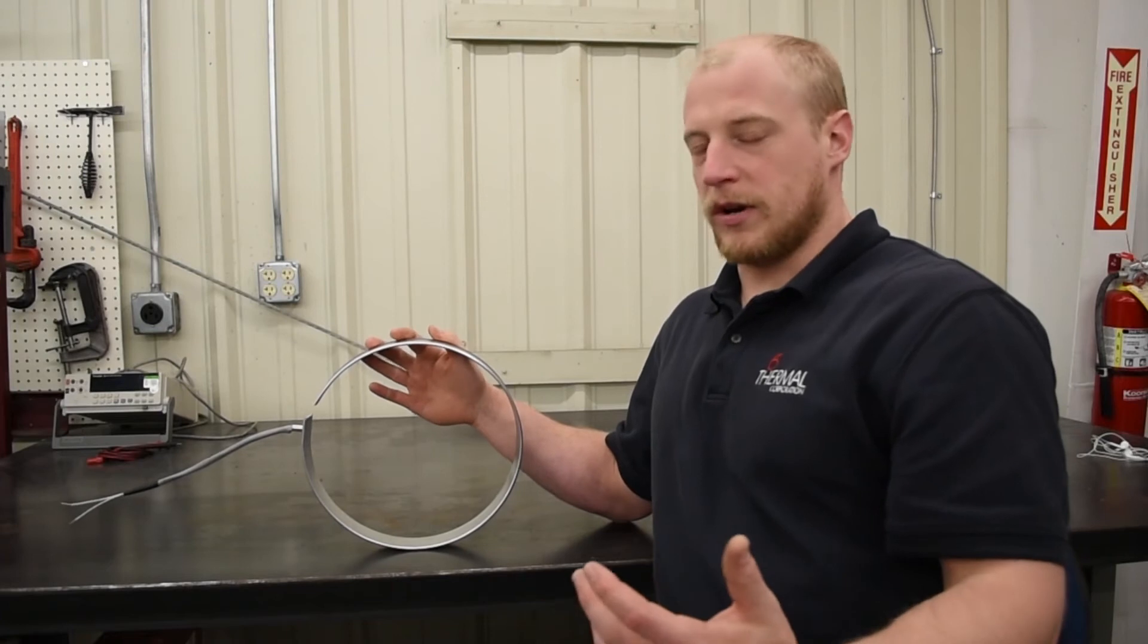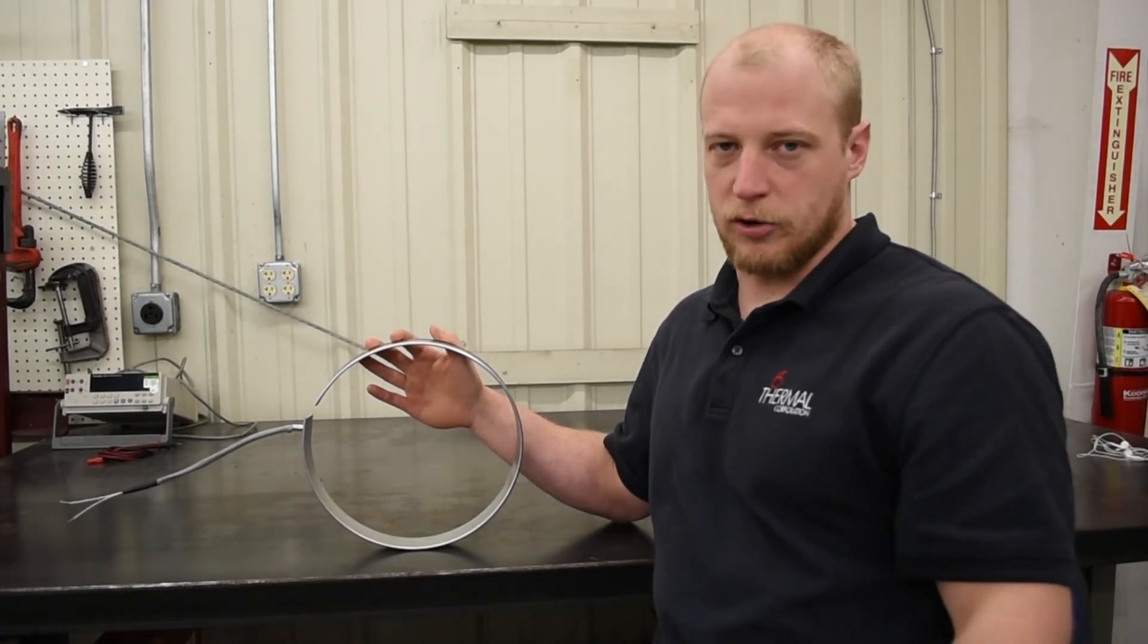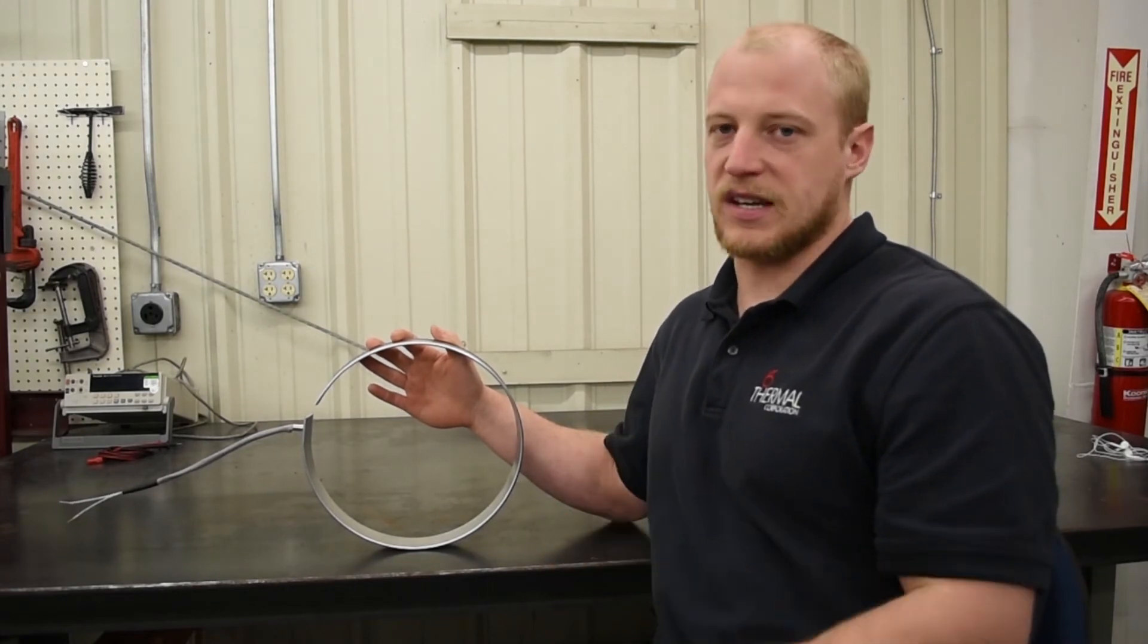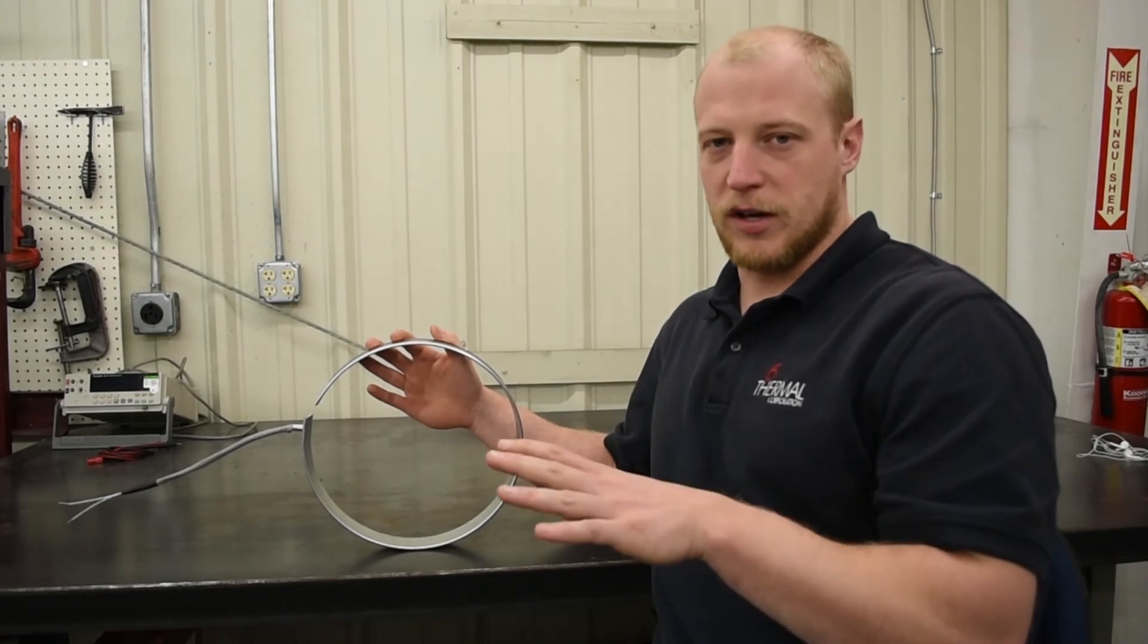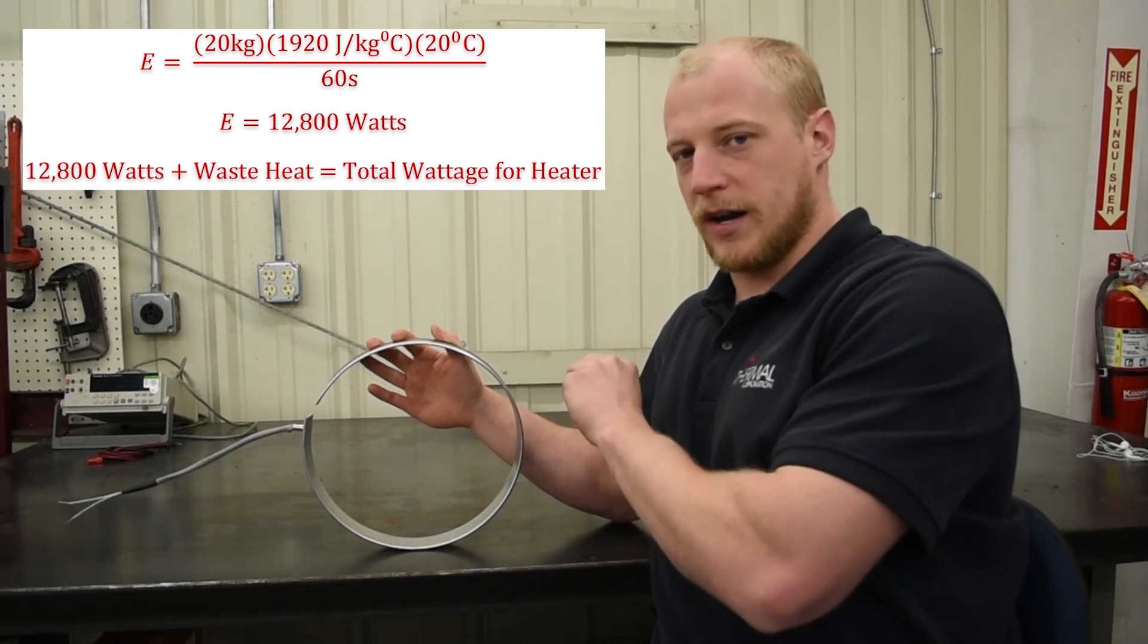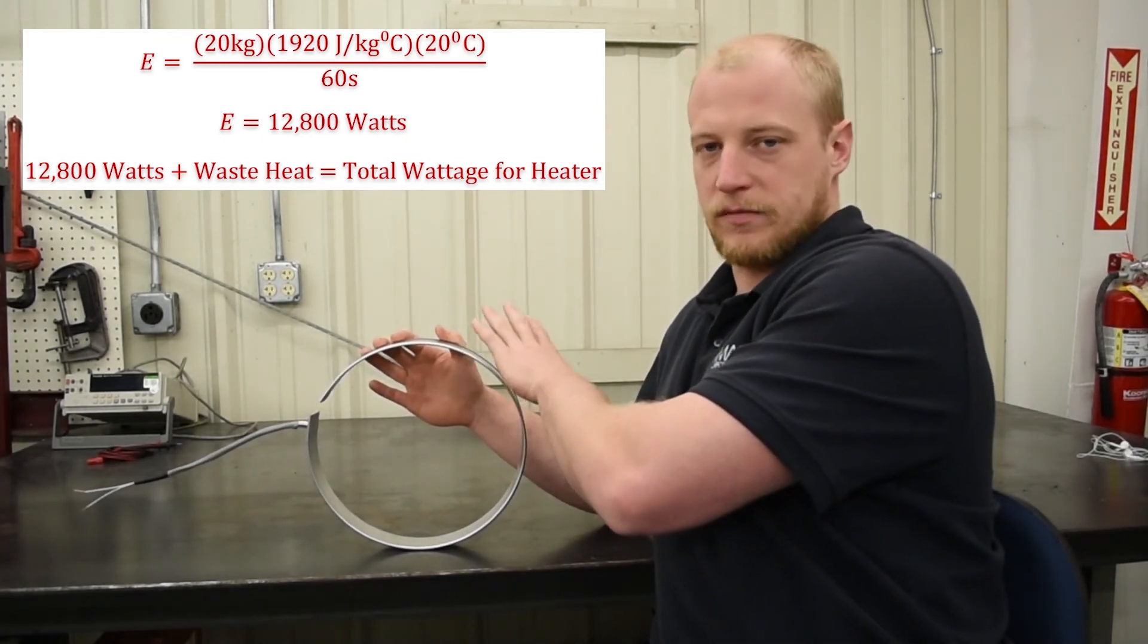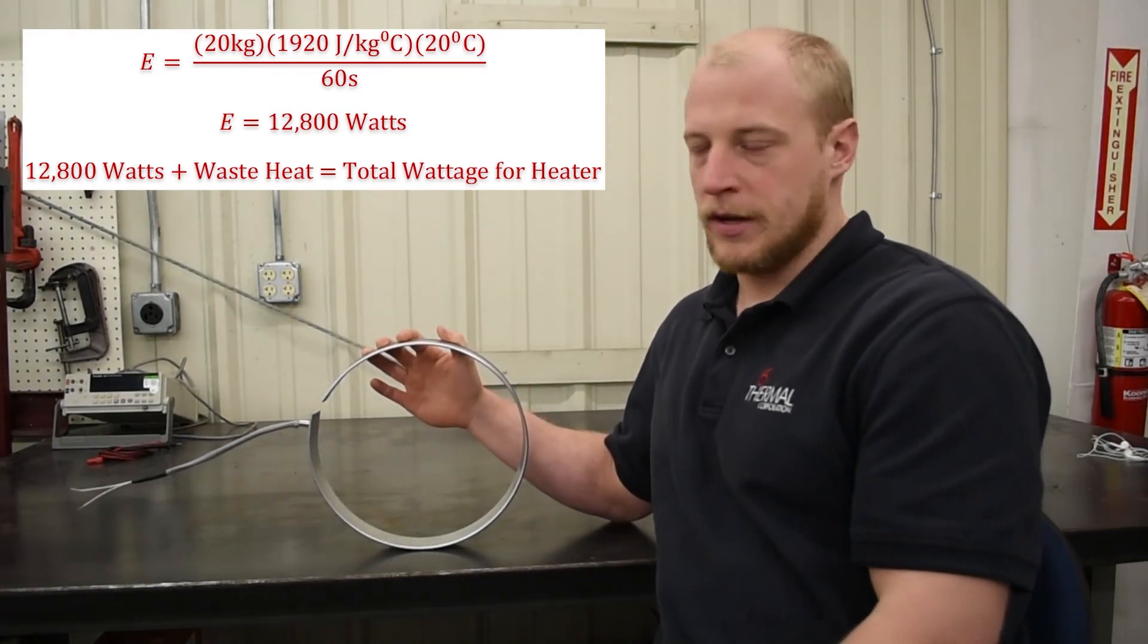Let's say we want to heat a chunk of plastic that weighs 20 kilograms. We want to heat that up by 20 degrees Celsius, and we want to do that every minute. We plug in all those numbers and that gives you a wattage. You then take that calculated wattage, add it to the wattage from your waste heat from the graph, and that's the wattage you need in your heater. That will usually get you pretty close.